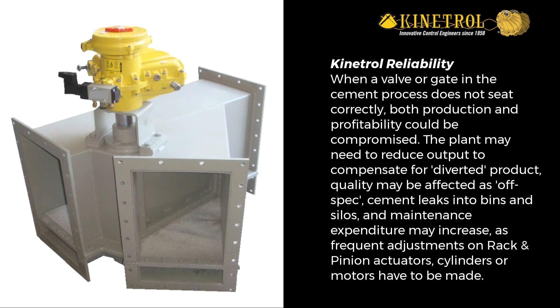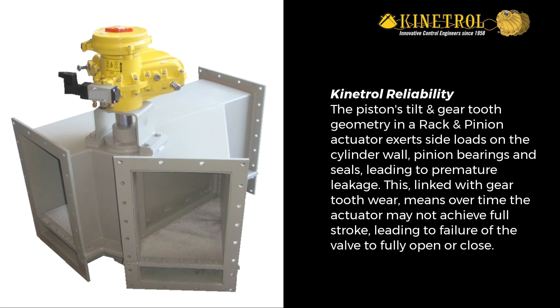Accuracy: when a valve or gate in the cement process does not seat correctly, both production and profitability could be compromised. The plant may need to reduce output to compensate for diverted product; quality may be affected as off-spec cement leaks into bins and silos, and maintenance expenditure may increase as frequent adjustments on rack and pinion actuators, cylinders, or motors have to be made. The piston's tilt and gear-tooth geometry in a rack and pinion actuator exerts side loads on the cylinder wall, pinion bearings, and seals, leading to premature leakage.